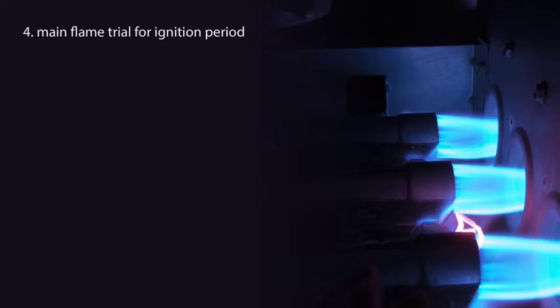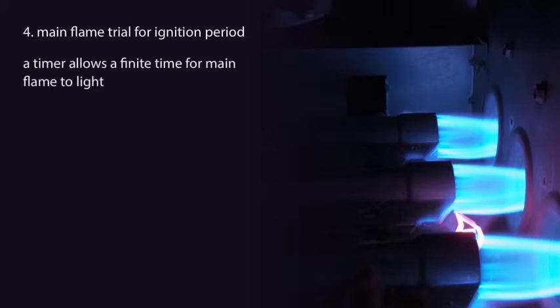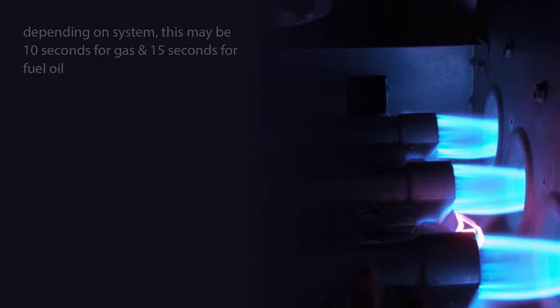The main flame trial for ignition period. Once a pilot is lit and the main gas firing rate control valve is at a minimum position, the main automatic safety shutoff and blocking valves open while the vent valve, if it exists, closes. A timer allows a finite time for the main flame to light. This period of time is called the main flame trial for ignition period.